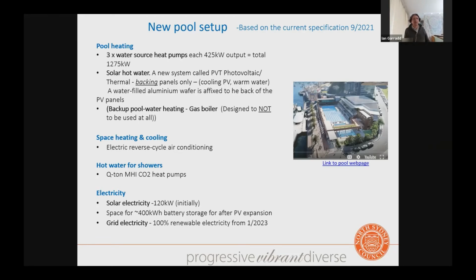I think that's mainly due to the large heat capacity that water has. It's a slightly more expensive setup, but when you've got very efficient, very large mass of heat in the harbour next door, that's the most effective heat source. We'll also be using solar hot water, but not straight solar thermal panels as previously. Instead we'll use a backing panel called a PVT, or photovoltaic/thermal backing panel - it's a water-filled aluminium jacket affixed to the backside of the solar PV panel, and the idea is to cool the PV panel while heating the water. There are dual benefits there because a cool solar panel generates more electricity.